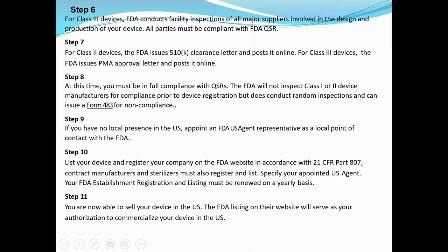So if you have no local presence in US, you have to appoint your US agent. That is a mandatory requirement. And also there is one more requirement, your firm has to register. So FEI, that is firm establishment, has to be there prior to application. So whenever a medical devices filing is done, we have to first ensure that our firm is registered there and we have appointed a US agent. Then list your device and register your company on the FDA website. This I have already mentioned as per 21 CFR Part 807.